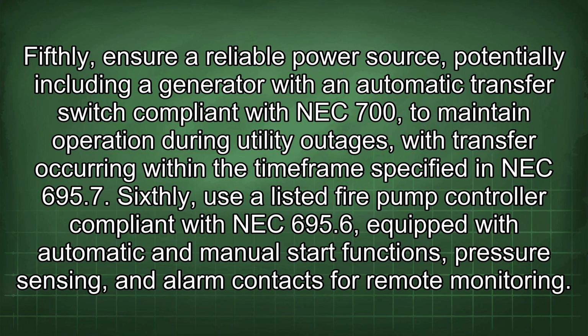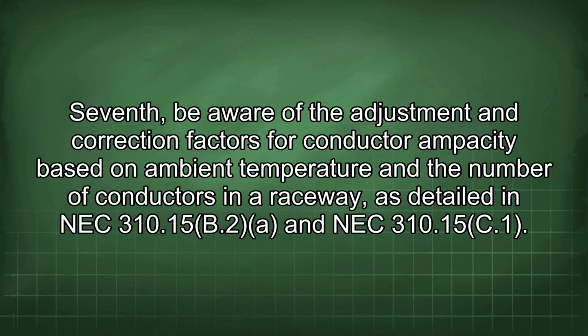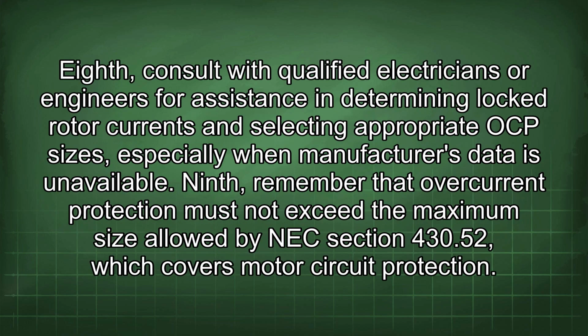Sixthly, use a listed fire pump controller compliant with NEC 695.6, equipped with automatic and manual start functions, pressure sensing, and alarm contacts for remote monitoring. Seventh, be aware of the adjustment and correction factors for conductor ampacity based on ambient temperature and the number of conductors in a raceway, as detailed in NEC 310.15(B)(2) and NEC 310.15(C)(1). Eighth, consult with qualified electricians or engineers for assistance in determining locked rotor currents and selecting appropriate OCP sizes, especially when manufacturer's data is unavailable.